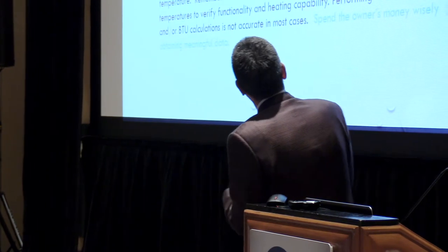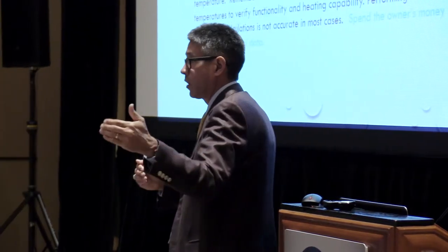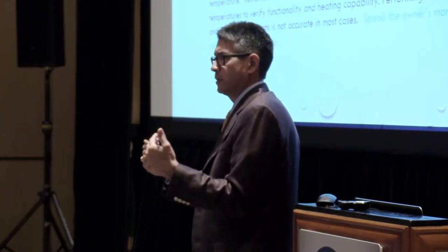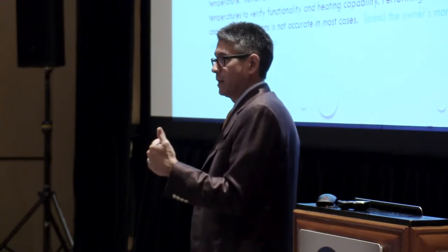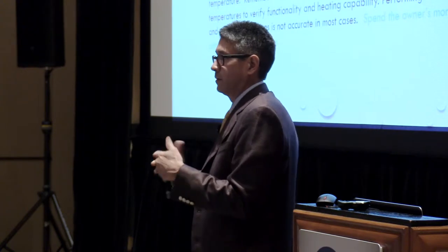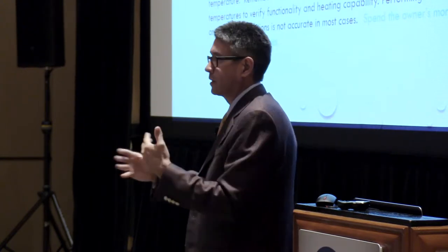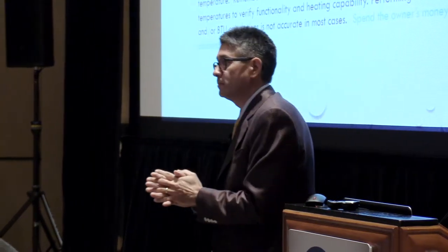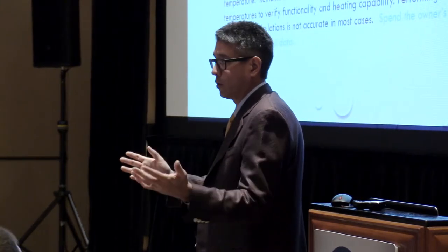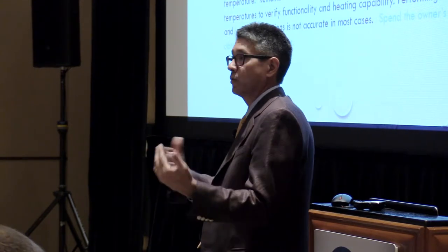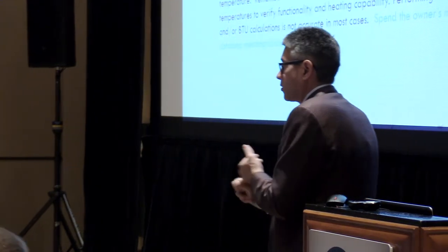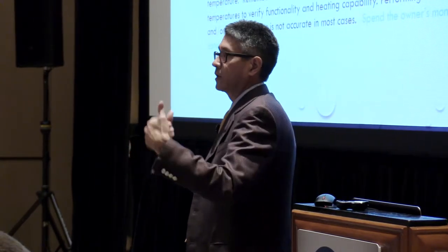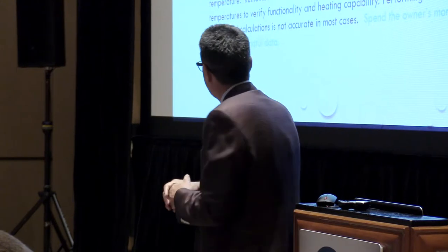We can balance it under control and try to set every valve to design water flow. But once again, we're almost back to the point of trying to simulate diversity and what that's going to get us. It might work on a building that doesn't have a lot of square footage or a lot of coils. But then again, you can go back and retest and see where your different options are. So you get a lot of coils, a lot of square footage. You really have to start stepping back and even looking at it further and figure out where your water is going to be and that type of thing.